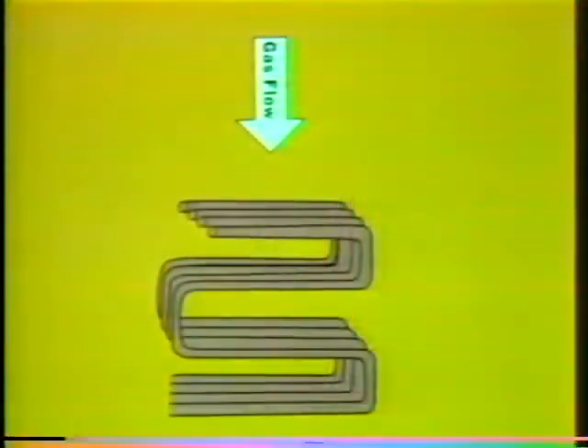In the pendant type arrangement, the tubes are set up so they pass vertically across the gas flow several times. This way, the steam in the tubes is exposed to the hot gases longer, providing a better chance to absorb heat. Super heaters can also be built with their tubes running horizontally. Whether your plant's boiler uses the vertical or horizontal type depends on the boiler design. Often, boilers have both horizontal and vertical tube arrangements placed in a number of locations throughout the path of hot gas. Larger boilers might have several sections of different kinds of super heaters.